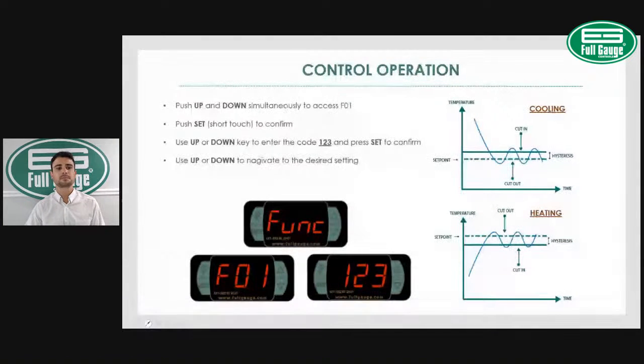So again, for changing the settings, we push up and down simultaneously, function F01, set, and we use the up or down keys to navigate to the code 123. Once we are there, set, and we can change any of the controller functions. So let's say we want to change F02. Here is my set point, my cutout temperature. Let's bring that up to 90.